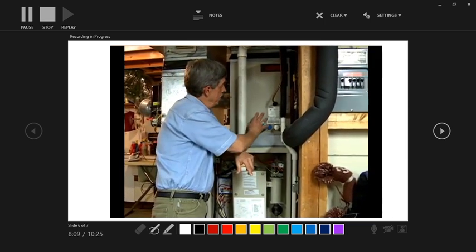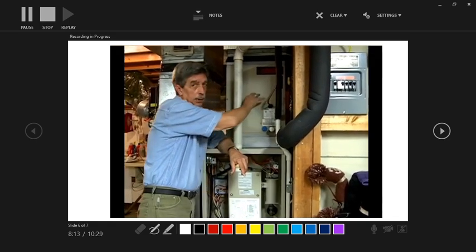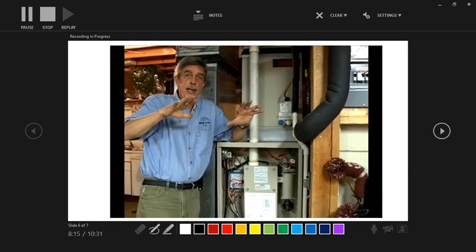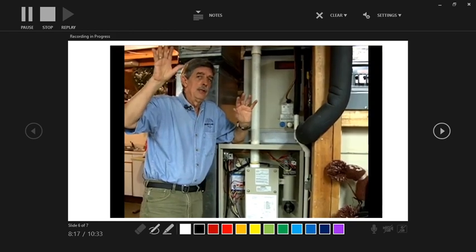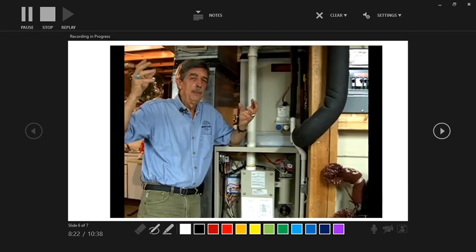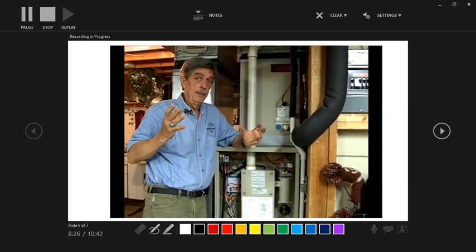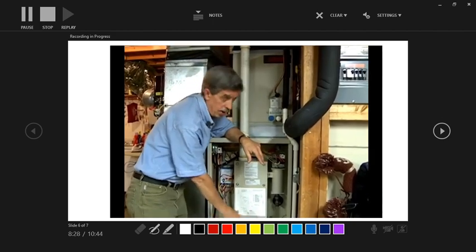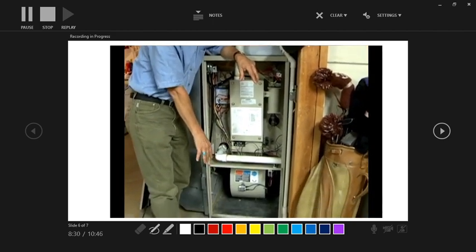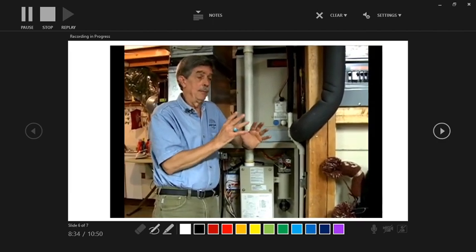If it is low in refrigerant, another thing that can occur is that you can get ice on your coil in here, and it'll actually kind of start blocking the airflow. You'll notice that it's not cooling upstairs as it used to. Feels a little humid up there, and so that'd be it. And then when the air conditioner is off for a period of some time, you'll see all sorts of water coming out underneath the floor and what have you. That's because the ice is melting. That is another sure sign the refrigerant levels are not up to snuff.